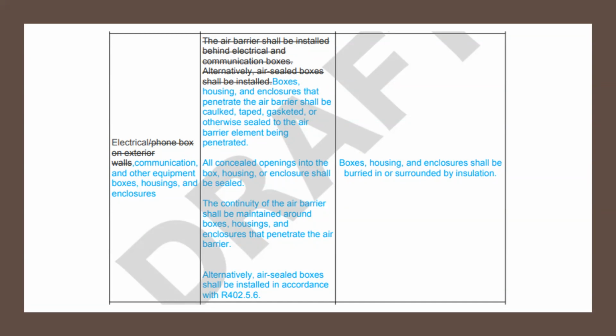So that's where I'm saying if they're air sealed boxes, then you need to follow that R402.5.6. Otherwise, this table is telling you how they need to be sealed. But just as we said a second ago, the insulation criteria to the right says it must be surrounded or buried by insulation. So squirting a bunch of polysil behind it does trap a lot of air bubbles. There is some insulation value to it. It will not be as much as putting a cut batt piece behind it. But if you're going to allow that and say it just needs to be filled up completely, and not just squirted on the box but a whole blob of polysil behind it, that can be adding as its insulation requirement. But it needs to be surrounded and buried.